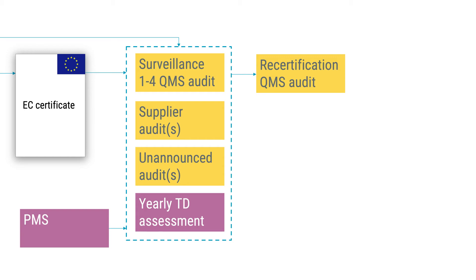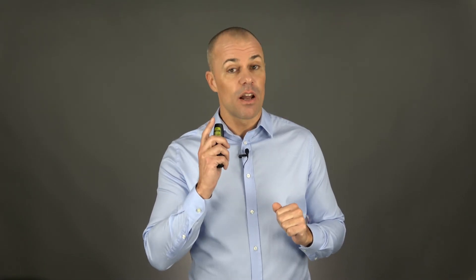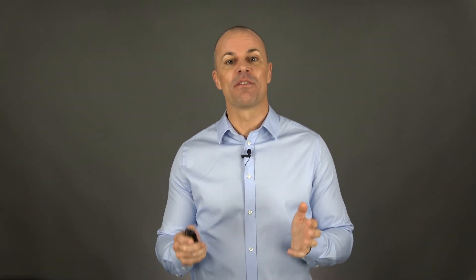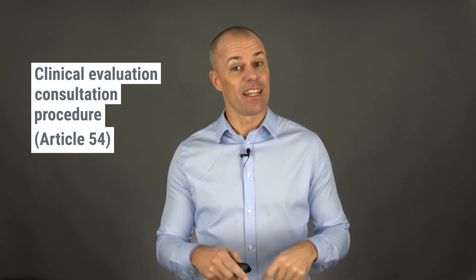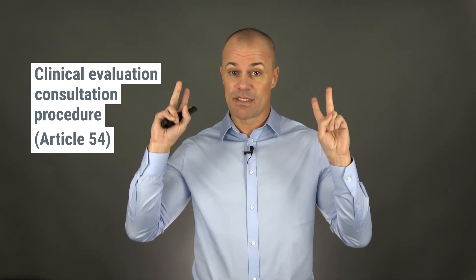Even though this is clearly stated in this MDCG endorsed document, I know that this is not always the case with all notified bodies. There will be a difference in the amount of technical files called in, since for class 3 devices, all devices need to have their technical documentation assessed before you get your EC certificate. For class 3 implantable devices and class 2b active devices intended to administer and/or remove a medicinal product, there is also the requirement to go through a clinical evaluation consultation procedure. This means the notified body shall send their clinical evaluation assessment report to a designated expert panel for a second opinion and their recommendation, which takes additional time.